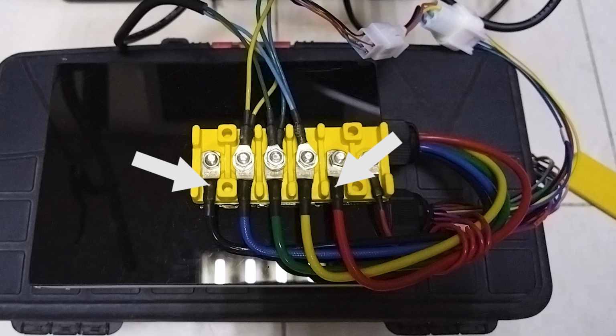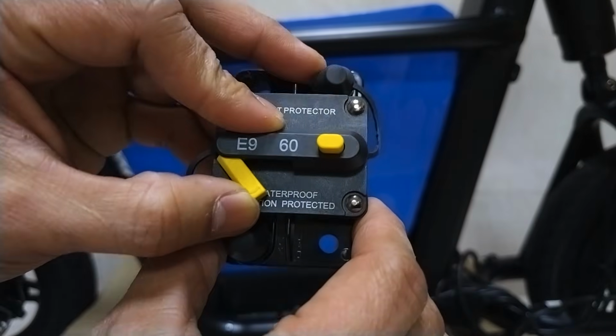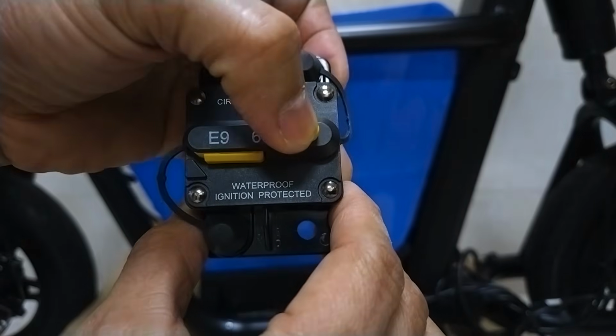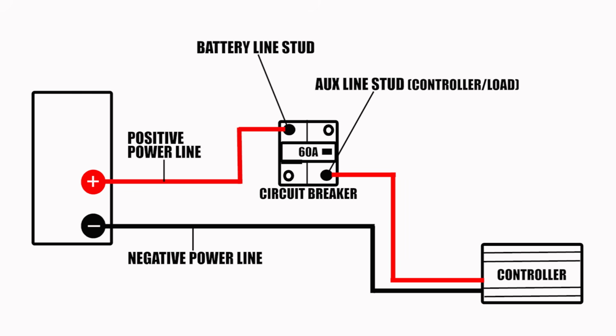These are the controller power line wires, black and red for the battery, and this is the extension wire for the battery output port. This is a 72 volt 60 amp circuit breaker, perfect for my 50 amp controller. This circuit breaker is for the main power positive line wire between the battery and the controller. The battery line stud goes to the power source or battery, while the auxiliary line stud goes to the controller or load.